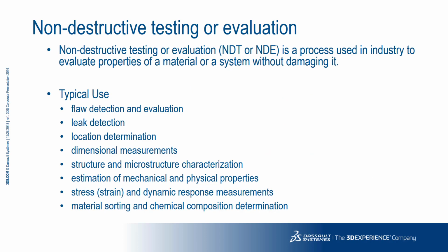Today we're looking at non-destructive testing, or NDT, which is the process used in the industry to evaluate the properties or integrity of a material without affecting its properties, so a device can continue to be used even after detailed inspection of its condition. In this presentation, we'll concentrate on two electromagnetic methods: magnetic flux leakage, as used for defect detection, and eddy current testing, which is sensitive enough to be used for gauging as well.